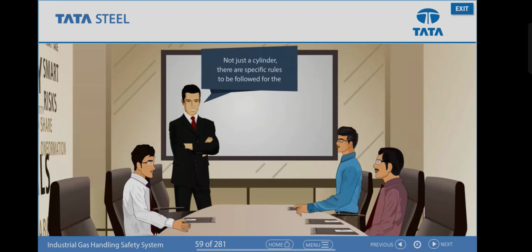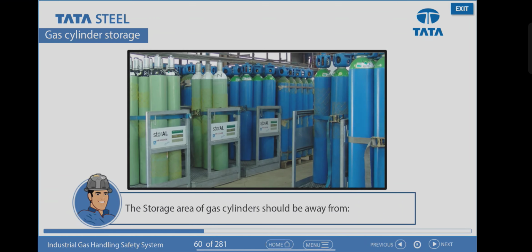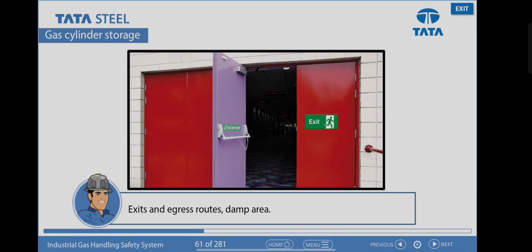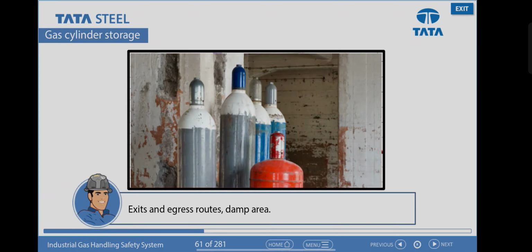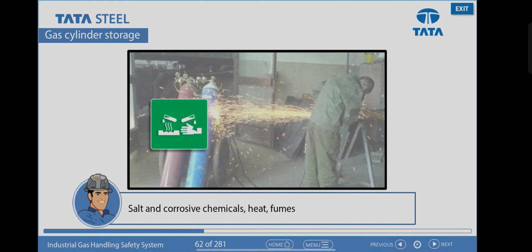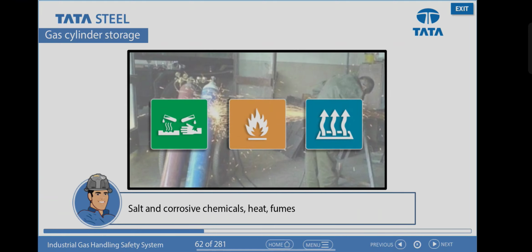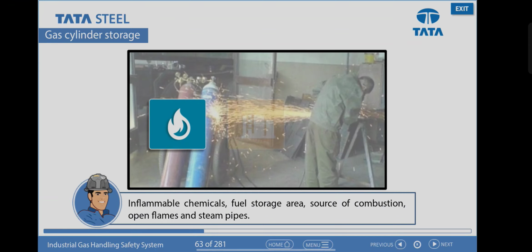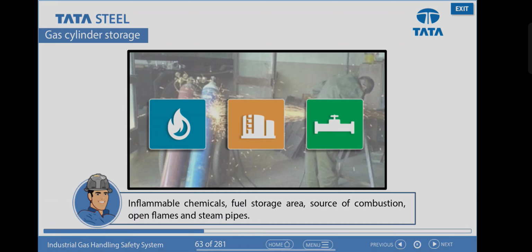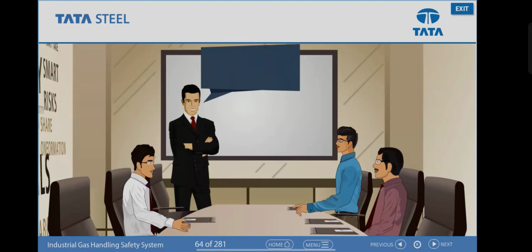Not just a cylinder, there are specific rules to be followed for the storage areas designated for storing gas cylinders also. The storage area of gas cylinders should be away from exits and egress routes, damp area, salt and corrosive chemicals, heat, fumes, inflammable chemicals, fuel storage area, source of combustion, open flames, and steam pipes. All gas storage areas have clearly placed signage indicating the do's and don'ts.